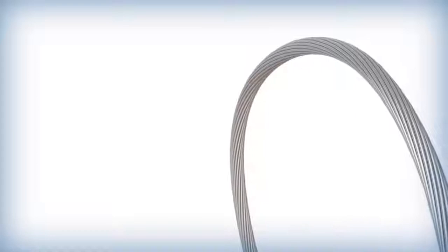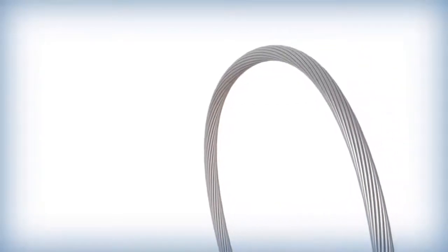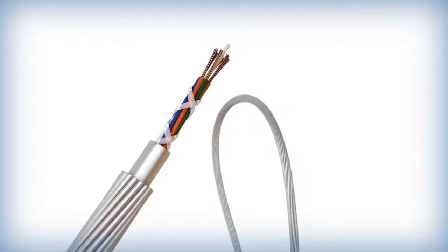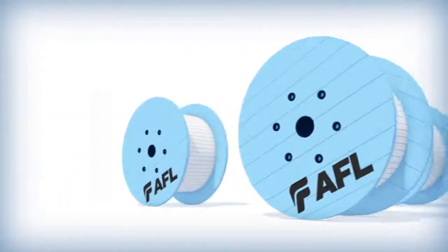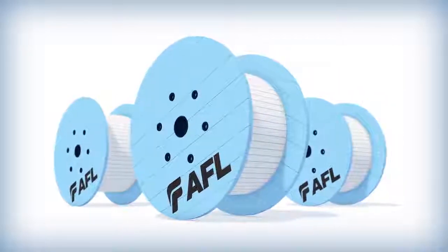During installations, care should be given to avoid tight bends and excessive tensions that could crush the OPGW's fiber bearing units. OPGW reels should always be in an upright position and never laid on their sides.